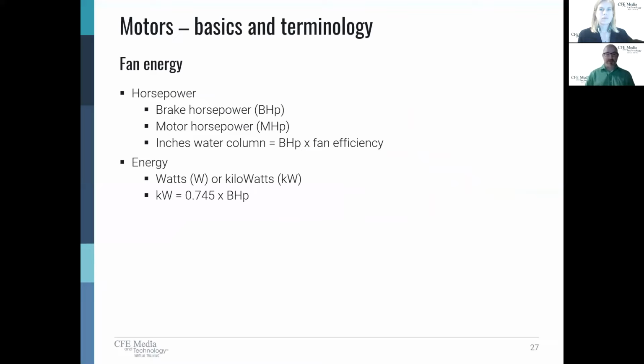Now, horsepower and motor brake power, right? What do these mean? What's the difference between a brake horsepower and a motor horsepower? Well, the brake horsepower is essentially the operating power that's required for that fan at that point. So you pick your fan's point on your fan curve. All right, I need, say, 7 horsepower in order to do my work. Now I have to make a motor selection, and that's going to be your motor horsepower, or MHP. So if I need 7 horsepower to make the fan work, I could, of course, pick a 7.5 horse. That's a standard size. Or I could pick a 10.